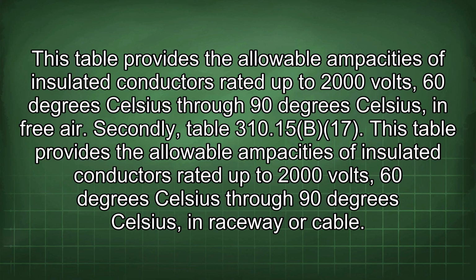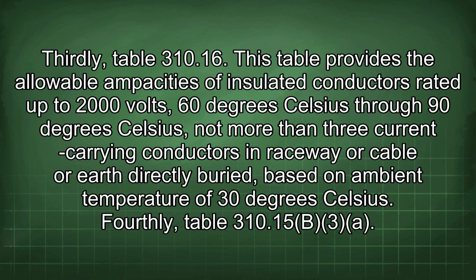Secondly, Table 310.15(B)(17). This table provides the allowable ampacities of insulated conductors rated up to 2000 volts, 60 degrees Celsius through 90 degrees Celsius, in raceway or cable. Thirdly, Table 310.16. This table provides the allowable ampacities of insulated conductors rated up to 2000 volts, 60 degrees Celsius through 90 degrees Celsius, not more than 3 current-carrying conductors in raceway or cable or earth directly buried, based on ambient temperature of 30 degrees Celsius.